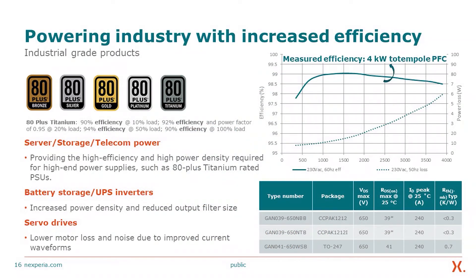Looking at industry efficiency benchmarks, these products deliver in excess of 99% efficiency as tested in a 4 kW totem pole PFC configuration. The 80 Plus standard defines industrial-grade power supply tiers, and gallium nitride power technology targets the highest tier: 80 Plus Titanium. This requires 90% efficiency at 10% load, 92% efficiency with power factor 0.95 at 20% load, 94% efficiency at 50% load, and 90% efficiency at 100% load — all met by this power GaN technology.